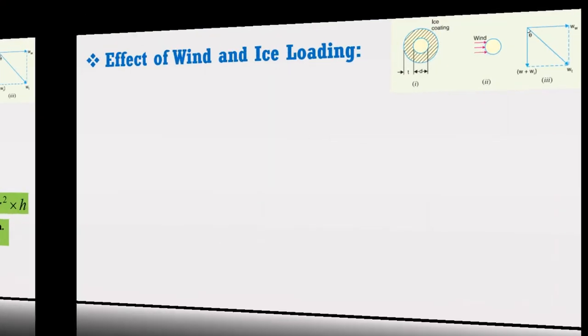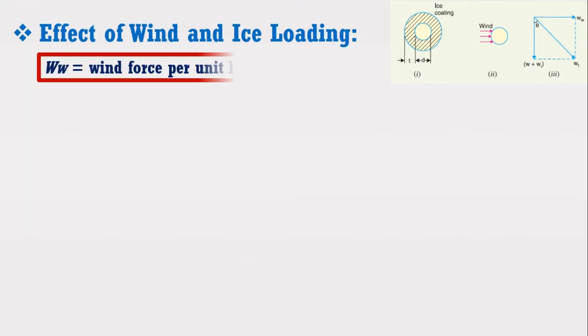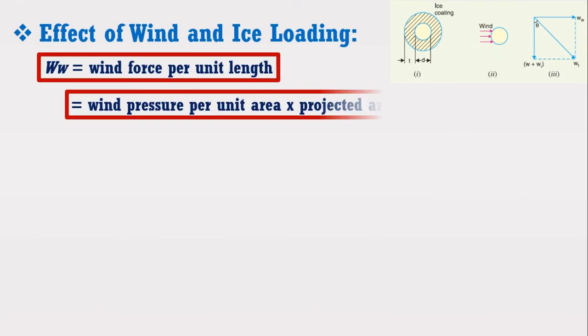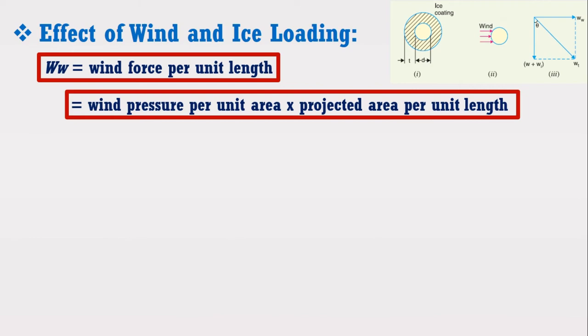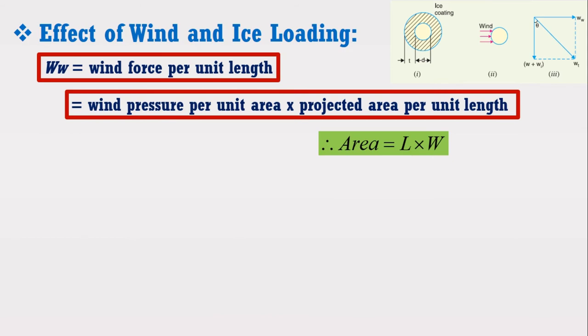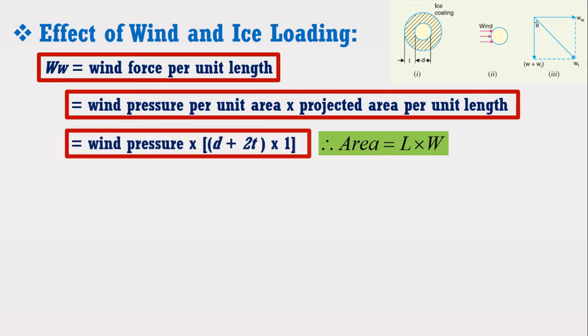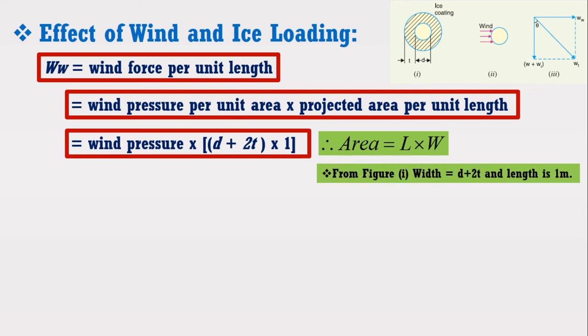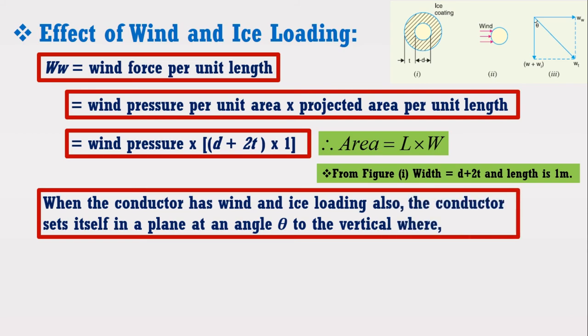Now, Ww is the wind force per unit length, equal to wind pressure per unit area into projected area per unit length. Since area equals length into width, and from the figure width equals d plus 2t with length as 1 meter, putting these values gives the wind force expression. It may be noted that when the conductor has wind and ice loading, it sets itself in a plane at an angle theta to the vertical.